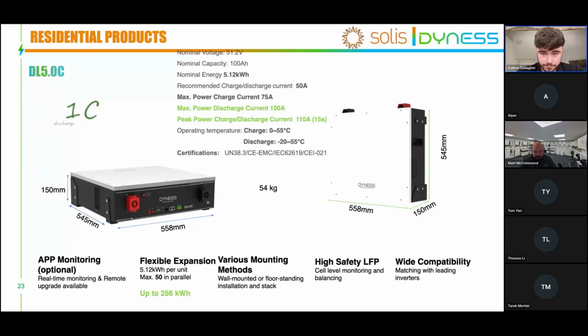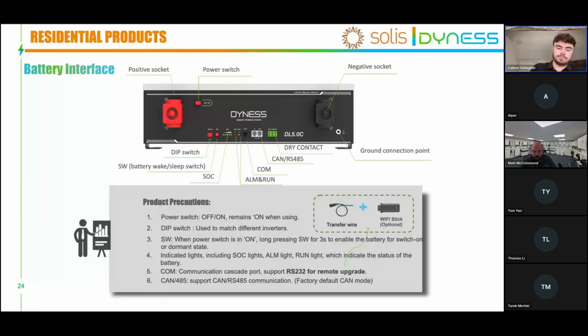It's a 5.12 kilowatt hour battery. This is rated for IP54, which isn't the IP65 like the H5B or the PowerBox Pro or the PowerBox G2. However, IP54 can be installed outside, we would just need some form of protection. You can install up to 50 of these in parallel. So this offers that wide range and flexibility in terms of capacity, which is very handy for installers when they're speccing jobs, and a wide compatibility with inverters as well. We're joined by Solis today, but we do offer that range as well.